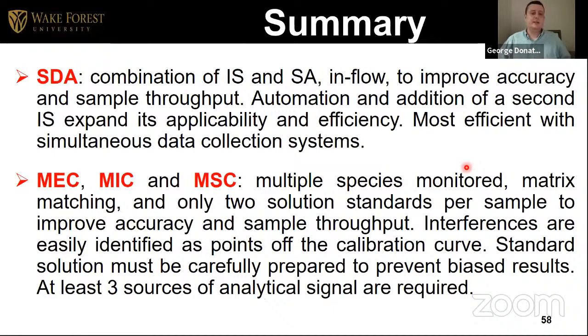So in summary, just so we wrap this up, SDA is a combination of internal standard and standard additions. It's done in flow, and can improve accuracy and sample throughput. We can do automation and add a second internal standard to expand its applicability. And it's most efficient if you can do simultaneous, but fast sequential also works. The other three methods, you need to measure several signals at the same time.